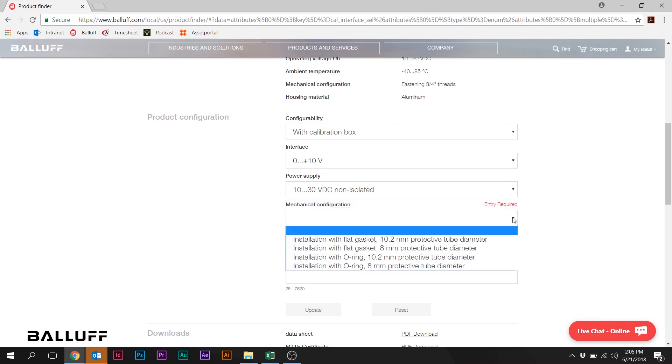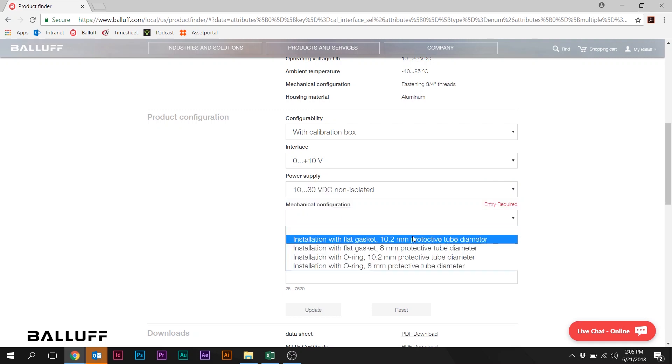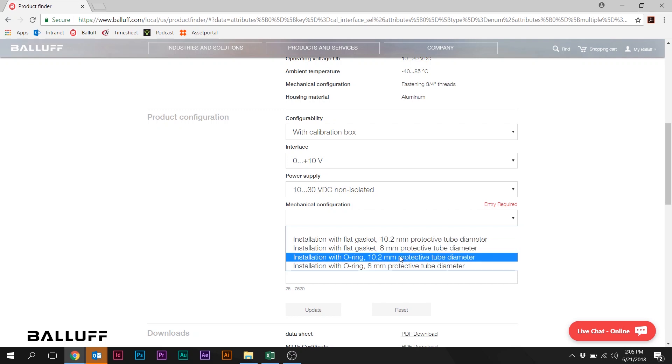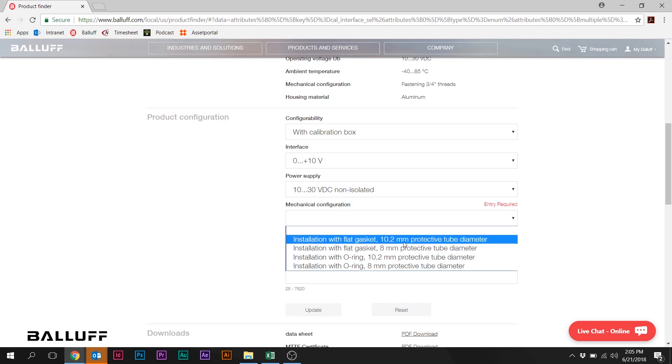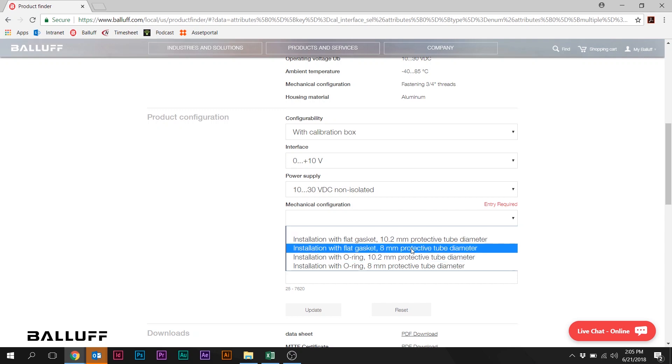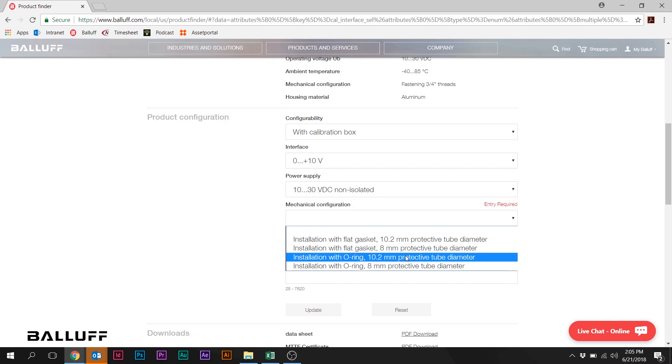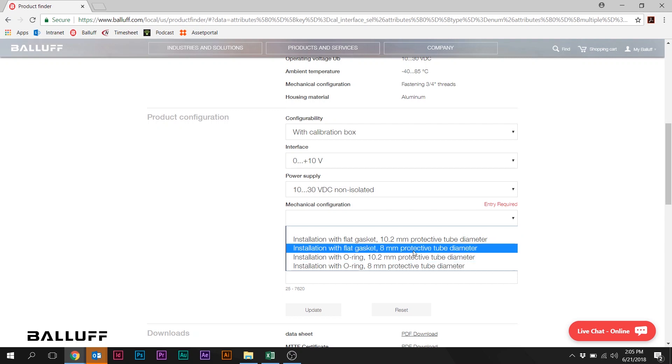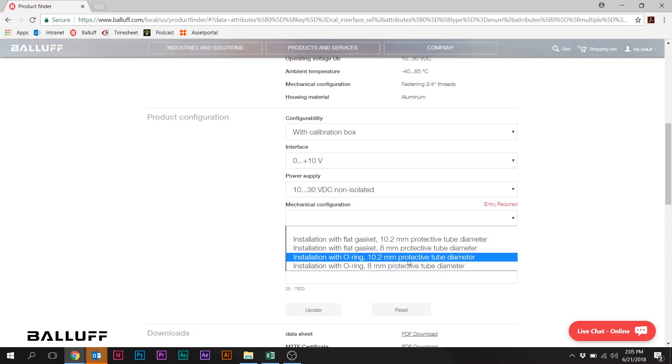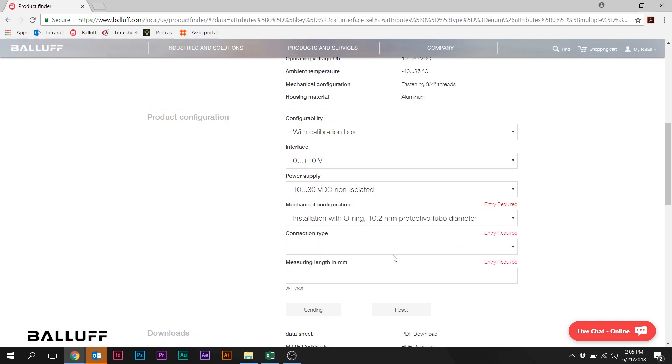Now we get down here to Mechanical Configuration. You've got a number of options here. What this really is talking about is whether we want a 10-millimeter diameter protective tube or an 8-millimeter diameter protective tube. The 10-millimeter is, again, by far the most common. We're going to pick the O-ring version. This is the standard Z-flange version in Balluff Nomenclature.